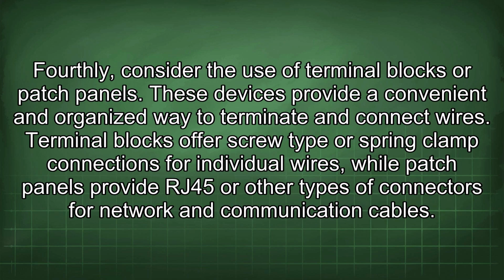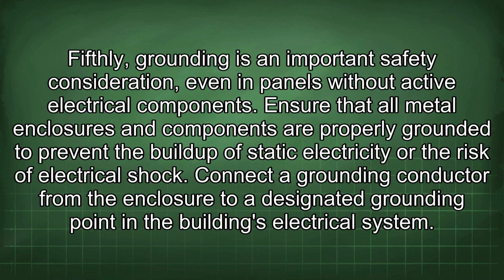Fourthly, consider the use of terminal blocks or patch panels. These devices provide a convenient and organized way to terminate and connect wires. Terminal blocks offer screw-type or spring clamp connections for individual wires, while patch panels provide RJ45 or other types of connectors for network and communication cables. Fifthly, grounding is an important safety consideration, even in panels without active electrical components. Ensure that all metal enclosures and components are properly grounded to prevent the buildup of static electricity or the risk of electrical shock. Connect a grounding conductor from the enclosure to a designated grounding point in the building's electrical system.